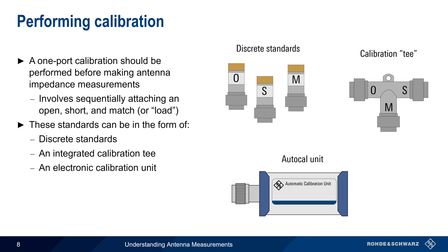Regardless of which type of calibration standard is used, this is usually a follow-the-prompts process, in which the VNA will indicate which standards are to be connected in which order and at which times. The entire process generally takes only a few minutes, with automatic calibration units tending to be much faster than using manual standards.